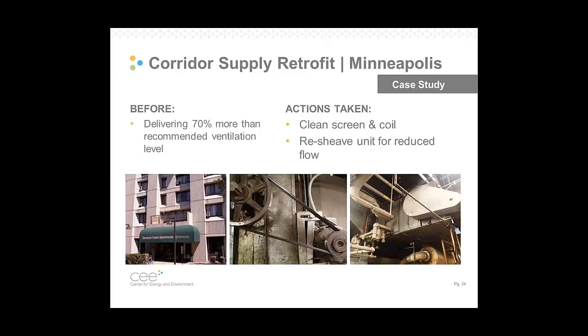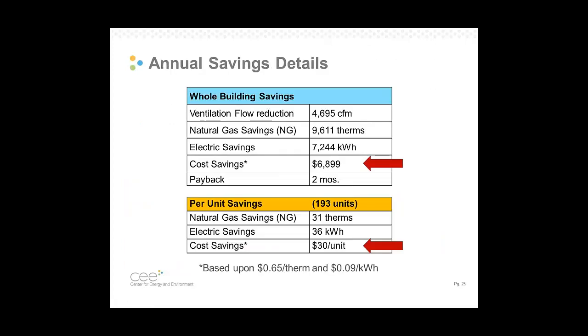Here's a retrofit we did on a supply system in Minneapolis. We found it was delivering 70% more ventilation air than was recommended for the building, even with a dirty intake screen and heat exchange coil. So still excessive, even though their intake screen and heat exchange coil were interfering with the flow. So we recommended that they clean the screen and the heat exchange coil, and then resheave these. Here's the sheaves or the pulleys here, changing those out for reduced fan RPM.